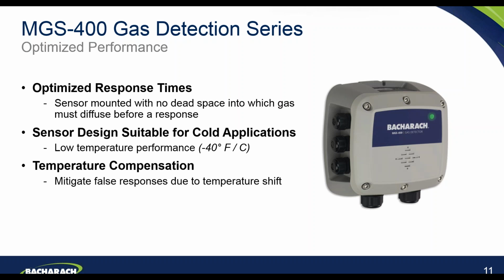And so in terms of the design of the housing for the 400 series, if you see the image on the right-hand side of your screen there, the faceplate with the small grills is the diffusion entry point for the gas. The sensor module essentially sits flush to the back of that faceplate. What that means is there is no dead space within the housing of the sensor. As soon as that gas starts to hit the housing of the sensor at the front of that plate, the sensor will start to respond very quickly.